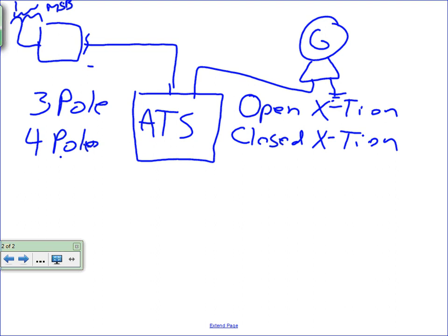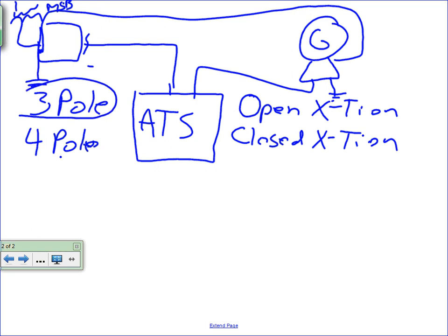Well, instead of bonding the generator here, we can actually run the ground for the system, right? You still have to ground that generator, but that's the enclosure ground, the equipment ground. But the actual ground from the generator, the power it's deriving, you can run that back to the same ground point as the service. So now the bond is still here. This isn't bonded over here. At that point, you have the same ground location. So all your neutral currents, no matter which device is running, are going to flow to this point. In that application, you can use a 3-pole.